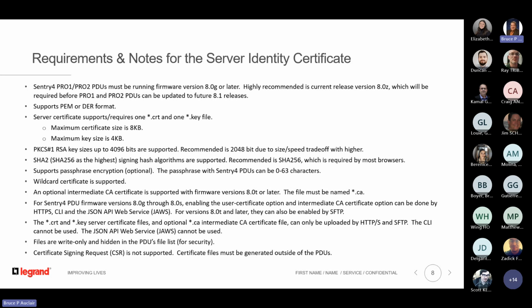So we won't discuss JAWS, since it only allows enabling the option, not installing the certificate. Once installed, the certificate files are not shown in the PDU's file list, which is only visible to administrator-level users — they're hidden from that list for security. Finally, note that the PRO1 and PRO2 PDUs do not have the ability to generate a certificate signing request; you must generate the request outside the PDU and then get the certificate signed by an outside authority.